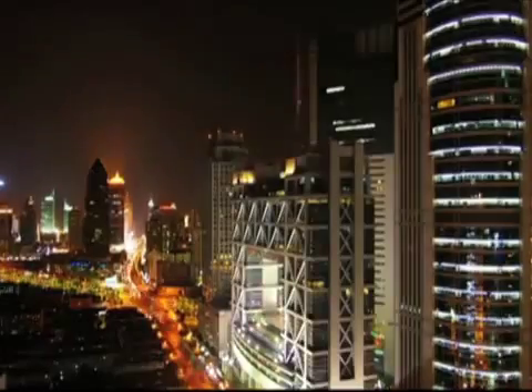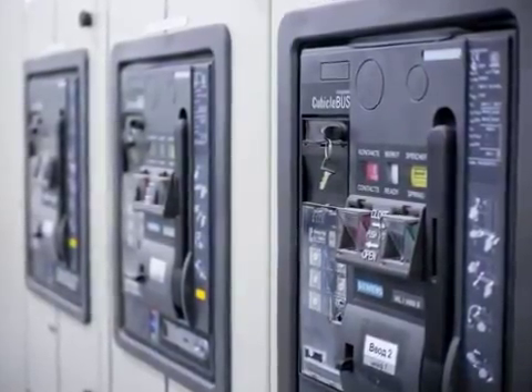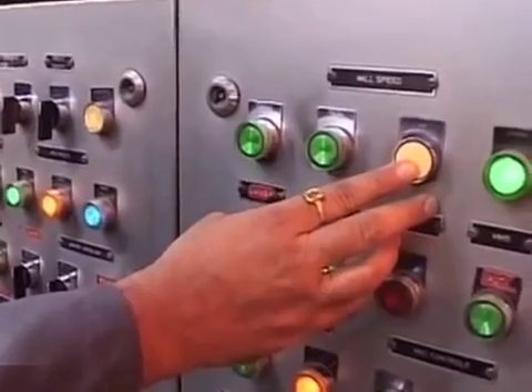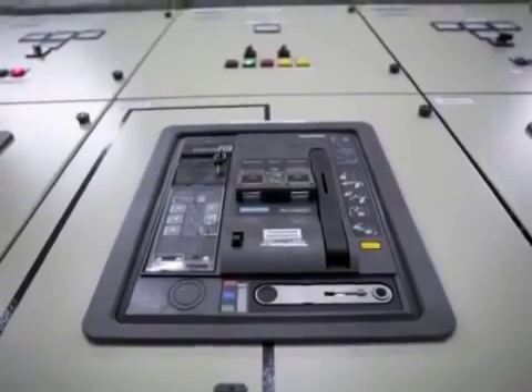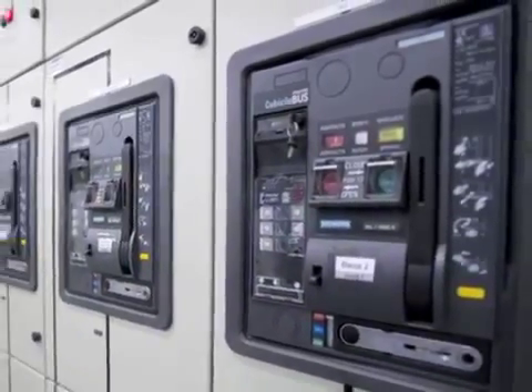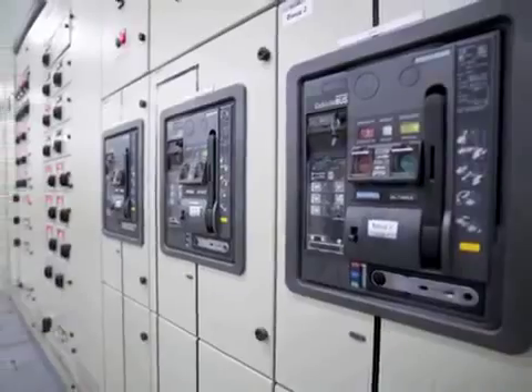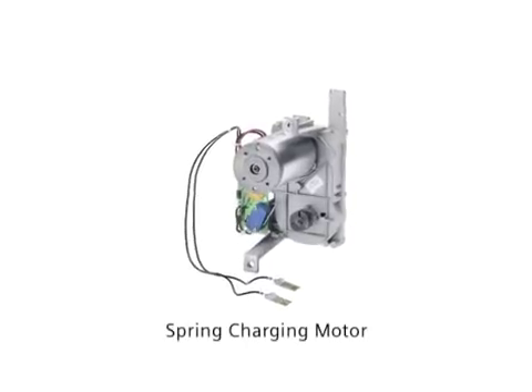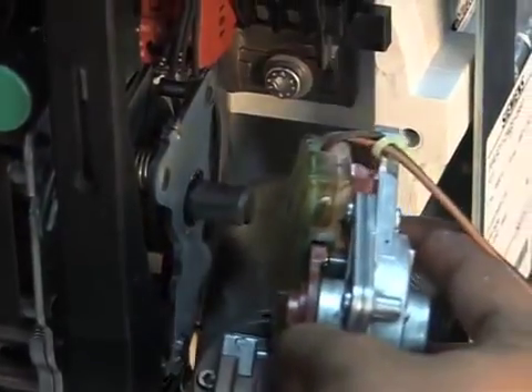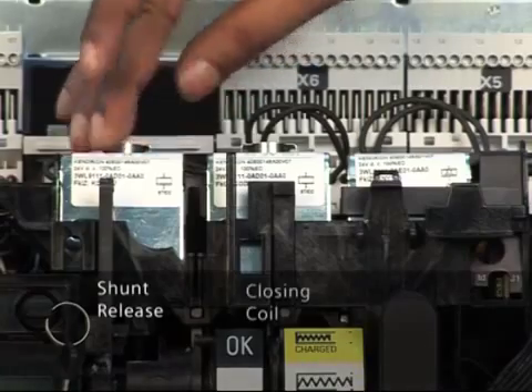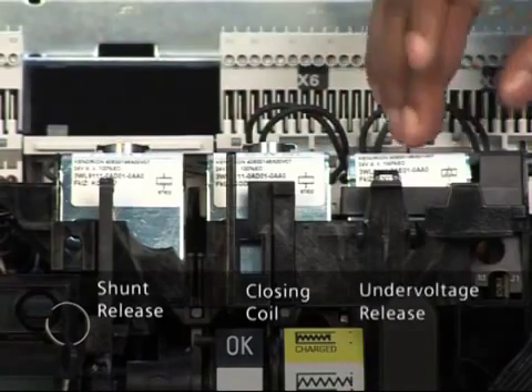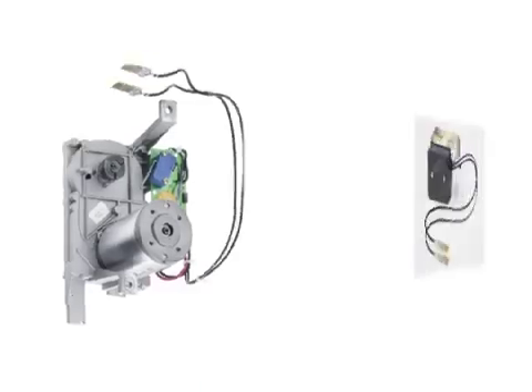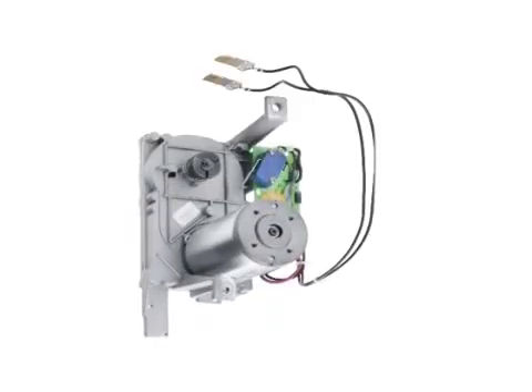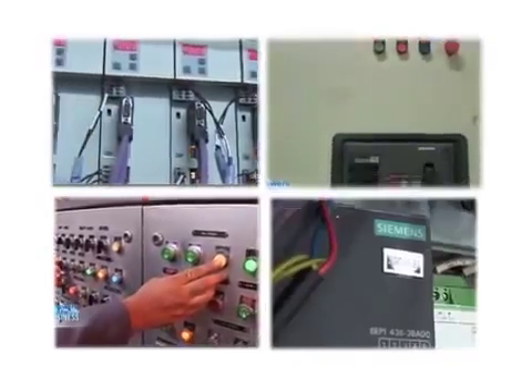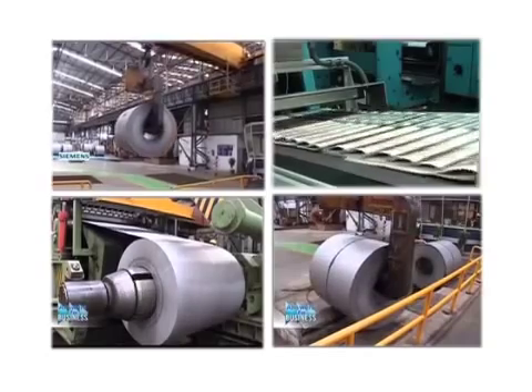Today, due to increased flexibility in low voltage power distribution, circuit breakers with remote and local operations require to be fitted with certain accessories, namely spring charging motor, shunt release, closing coil, under voltage release. The selection of accessories depends mainly on the control voltage and the process requirement.